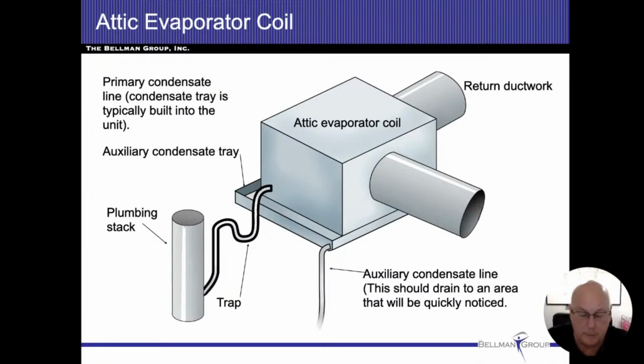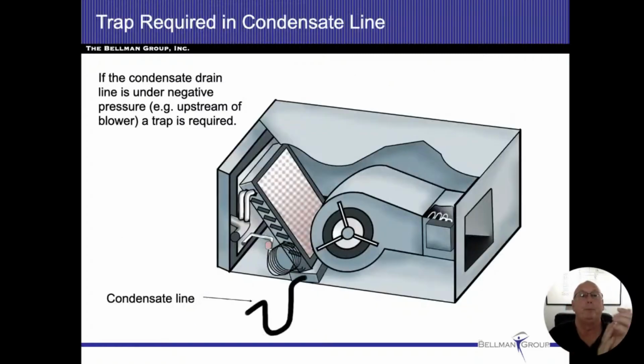Now you'll see a few different solutions to these. Some will have alarms in them. Some will have cutoff switches, so there are little floats. If it fills up with water, then the air conditioning system is going to shut down. Other ones are going to have another drain, but typically that drain is going to go someplace where it's noticeable, so you'll see the pipe out there. The pipe will always be out there. You should never see any water flowing from it. But if someday you go out there and you see that it's dripping out of there, that's telling me you've got a problem. All right, our primary drain is clogged and water's flowing out of the secondary drain. Somebody needs to get up there and make sure that the primary drain is freed up and drain the water as it should. All right.